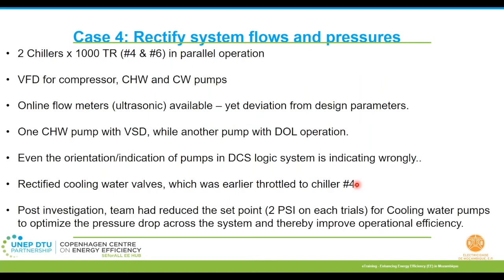So this is case 4, about rectifying your system flows and pressures. This particular facility had 2 chillers of 1000 TR capacity each, running in parallel. The facility had state-of-the-art technologies, with everything installed. There are variable frequency drives, control systems and monitoring systems in place. Everything was quite perfect in terms of installations. But the only problem was that you cannot rely completely on the control systems. Machines can only work to a certain extent. Ultimately, it is us, the humans, who have to do the job, right?